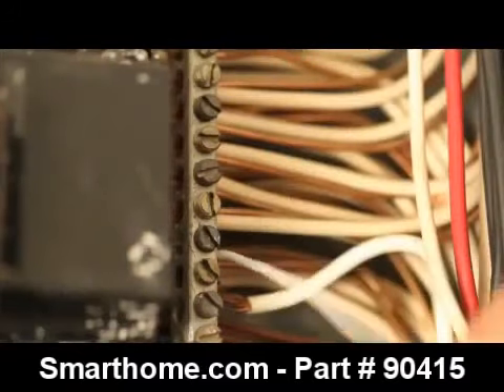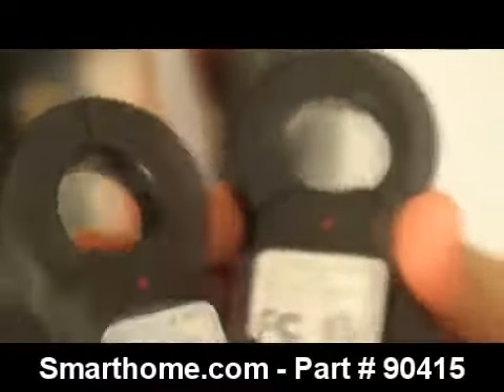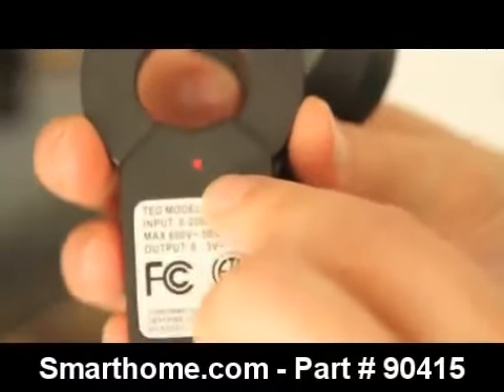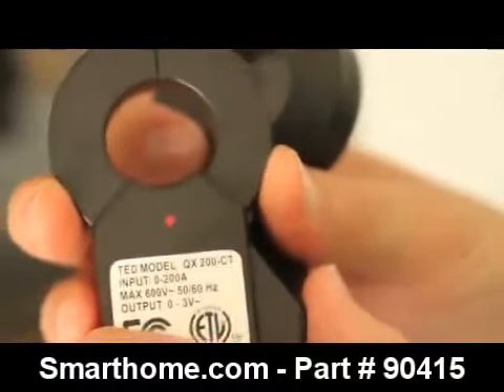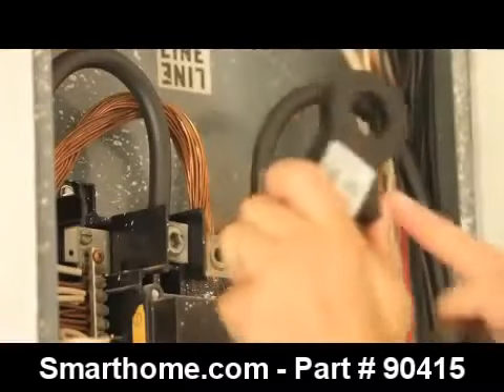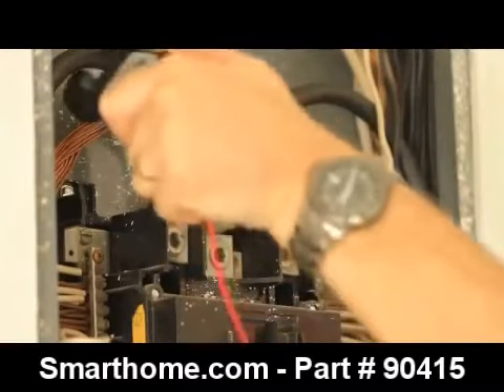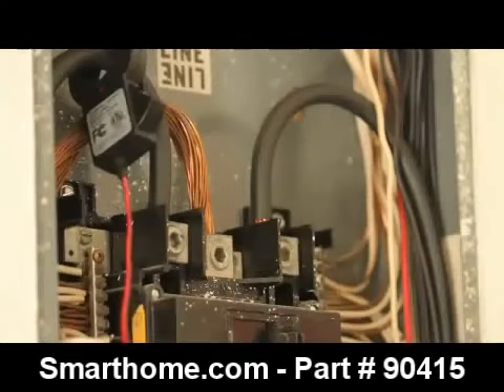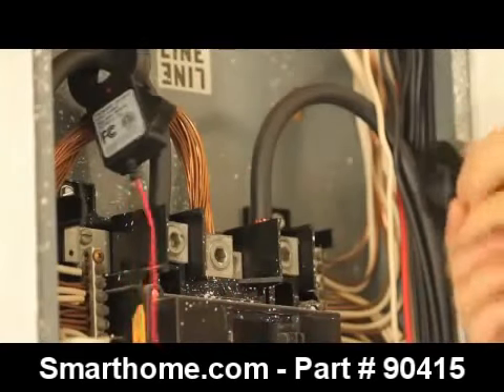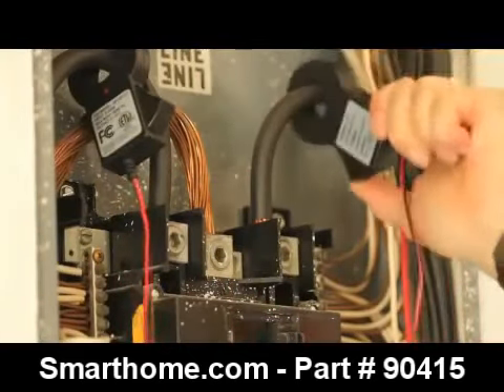Now that the MTU is installed, it's time to install and connect the current transformers. The CTs must be installed with the red polarity dots facing toward the source of power, in this case the utility meter. Making sure the red polarity dot is facing the correct direction, clamp one CT over each conductor.